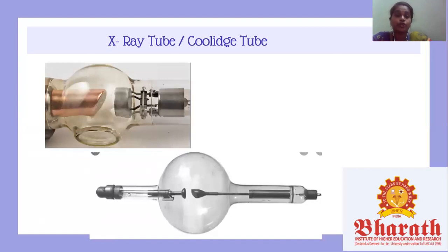The maximum energy of the X-ray is the same as the kinetic energy of the electron striking the anode. In addition to the X-rays produced at the focal spot of the anode, some undesirable X-rays are produced by electrons striking the other tube components.